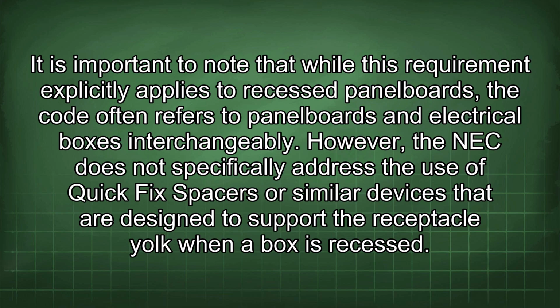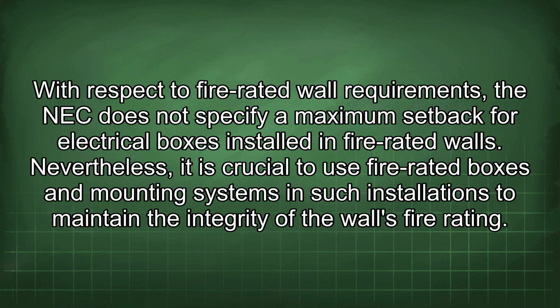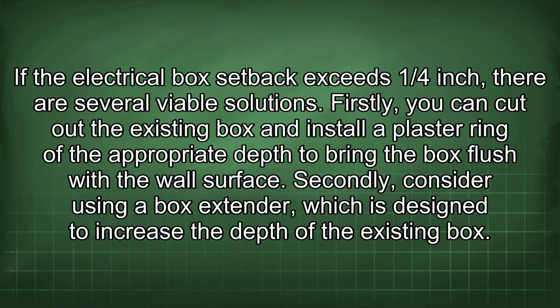However, the NEC does not specifically address the use of quick-fix spacers or similar devices that are designed to support the receptacle yoke when a box is recessed. With respect to fire-rated wall requirements, the NEC does not specify a maximum setback for electrical boxes installed in fire-rated walls. Nevertheless, it is crucial to use fire-rated boxes and mounting systems in such installations to maintain the integrity of the wall's fire rating. If the electrical box setback exceeds 1/4 inch, there are several viable solutions.